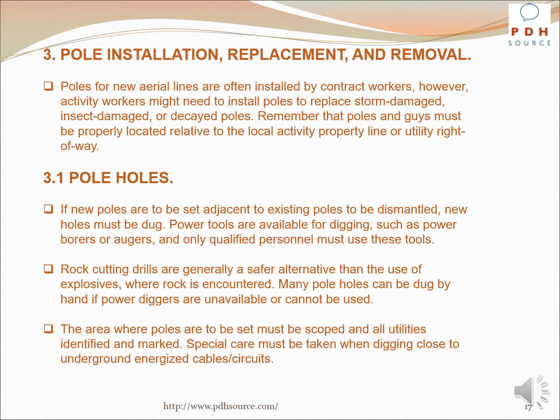Poles for new aerial lines are often installed by contract workers. However, activity workers may need to install poles to replace storm-damaged, insect-damaged, or decayed poles. Remember that poles and guys must be properly located relative to the local activity property line or utility right-of-way. If new poles are to be set adjacent to existing poles to be dismantled, new holes must be dug.